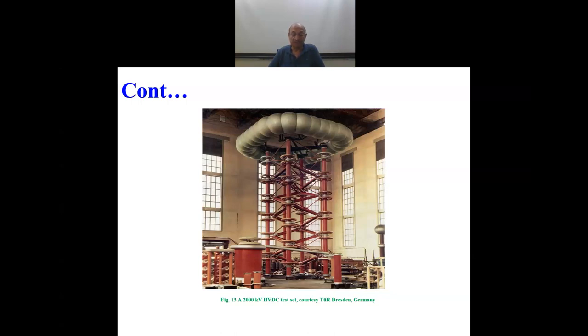So there are a number of stages, if I'm not mistaken, 1, 2, 3, 4, 5 stages. In 5 stages, each stage output would be 400 kV in this test set. And the electrode where you get such a high voltage is on the top, and there you can get a maximum to the order of 2000 kV DC output. So this is how the DC generation takes place, and this is how the DC generators are designed in the laboratories.